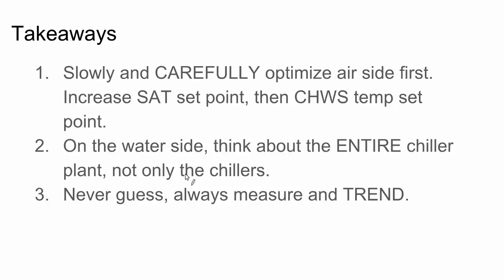And one helpful hint here is you have to normalize your trends based on the outside conditions. For example, if you're looking at the number of cooling tower fans that are running and the number of condenser water pumps and trying to figure out how much energy the whole chiller plant is using, but it's a cold day outside, and you're comparing that to what your summer operation is like, then the results of that analysis are going to lead you down the wrong direction. So be very careful about how you collect your data and how you make decisions based on that. Good luck.